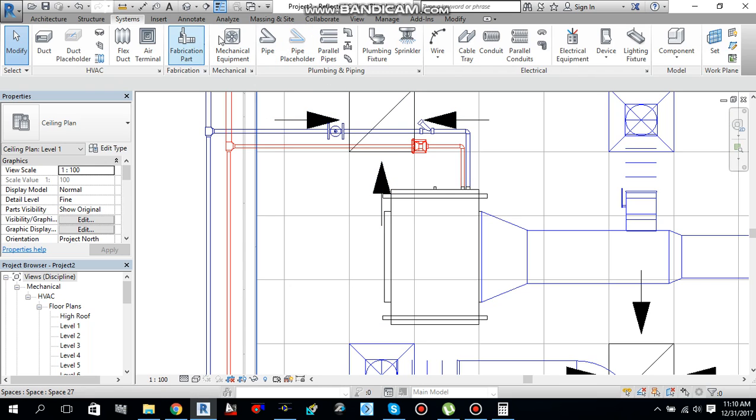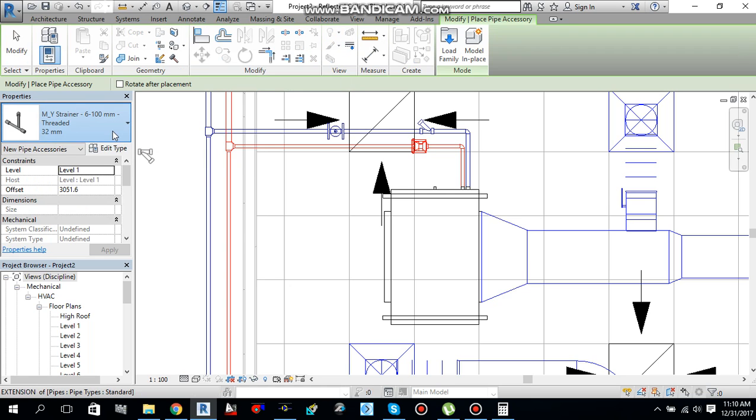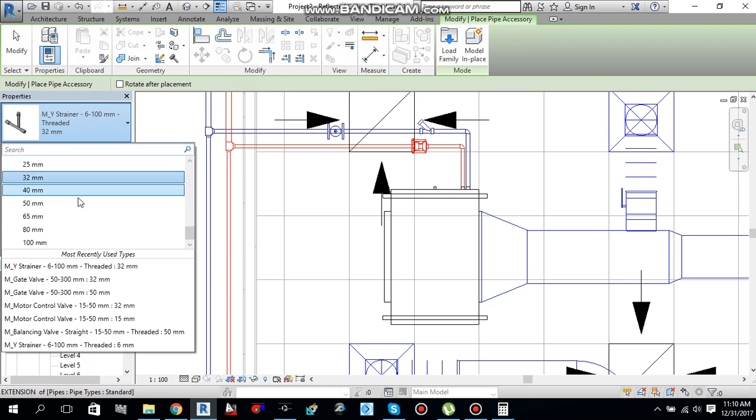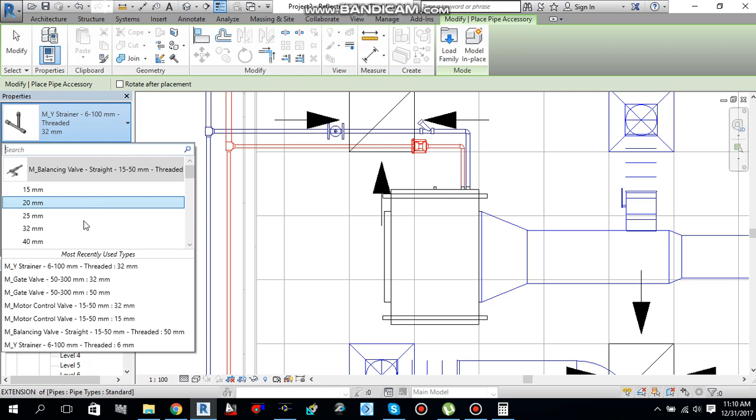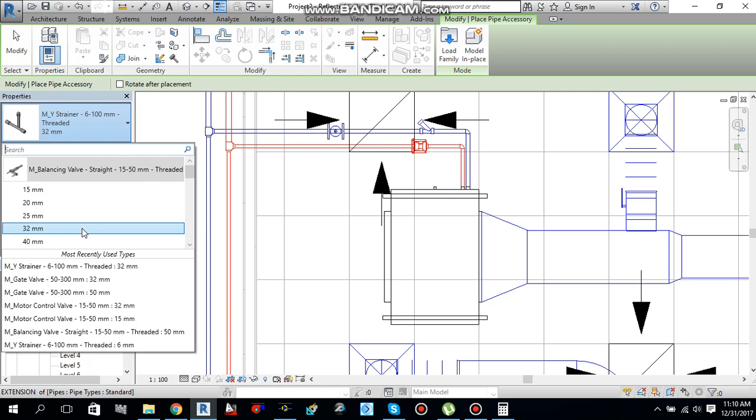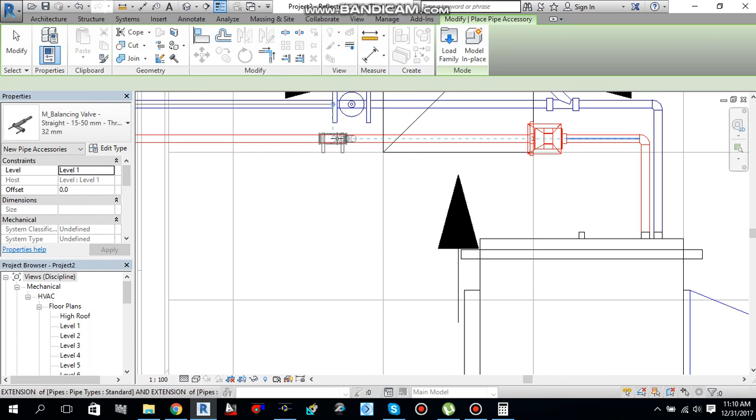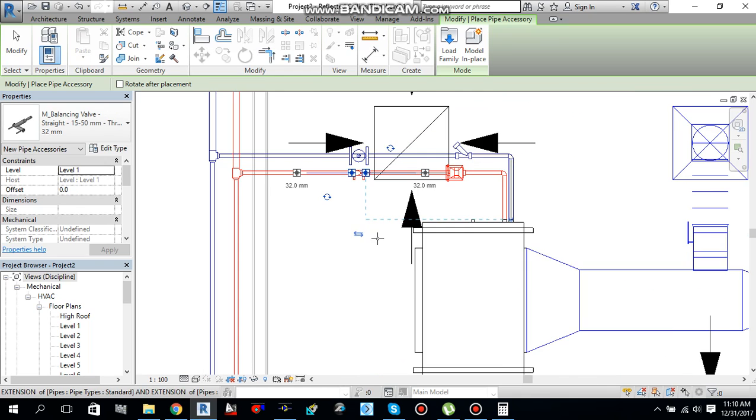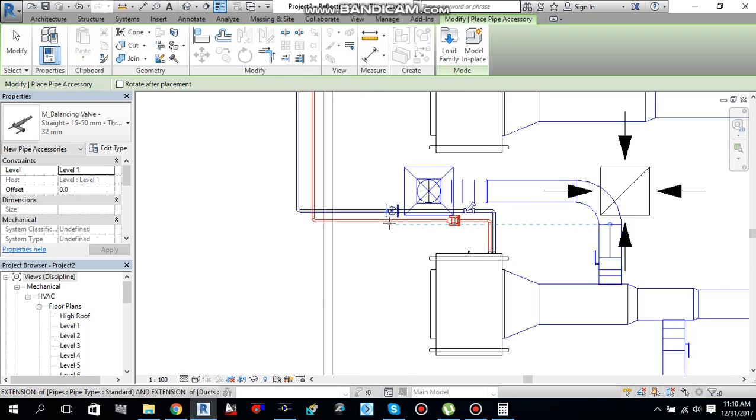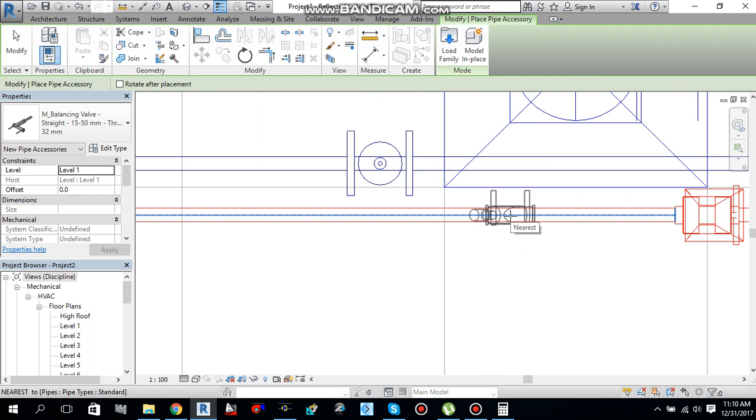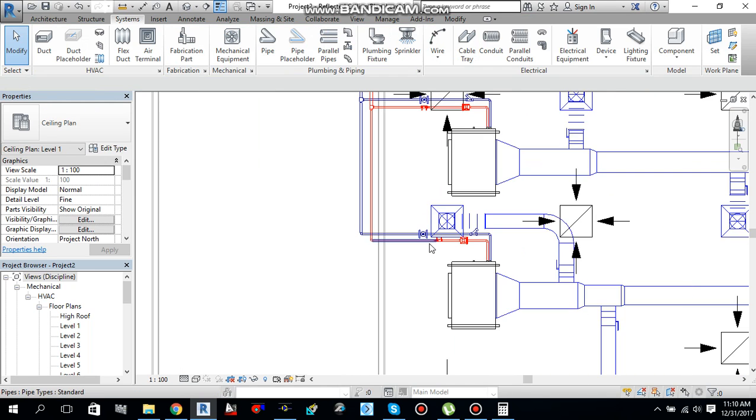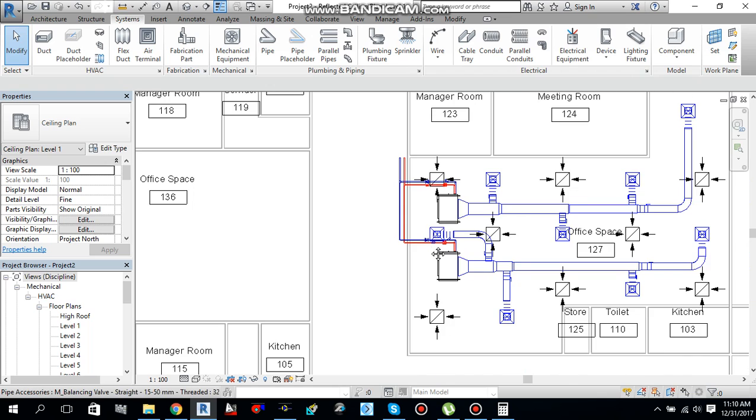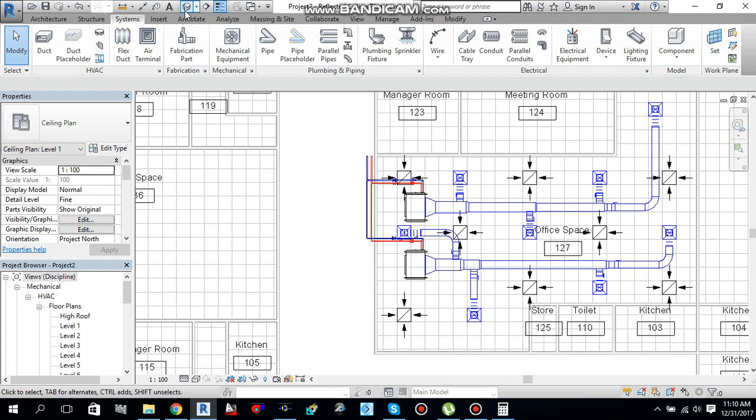One thing more I need to add over here, that is the balancing valve DRV double regulating valve. So again go to pipe accessories, system pipe accessories. I need to add balancing valve, this balancing valve threaded 32 mm. I need to add over here, just add it over here. Balancing valve one here and the second one here. Press escape, cancel the command.